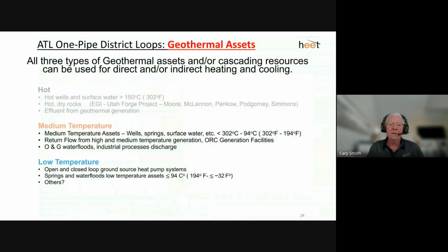Next slide. The next thing is we had to address what we could do with the thermal loop. What could we do with the thermal well? We're really talking about a medium temperature to low temperature asset that produces a certain amount of energy. The energy we start with is functionally 180 degree Fahrenheit water. We can take 100 degrees out of that, because this ambient temperature loop operates between the temperatures of 50 degrees Fahrenheit and about 95 degrees Fahrenheit. So it's safe. It's just regular water with low corrosion inhibitor and so forth.